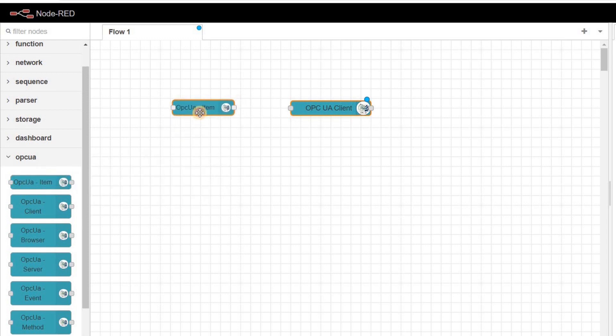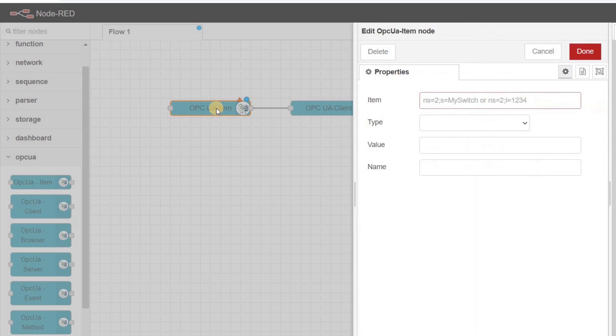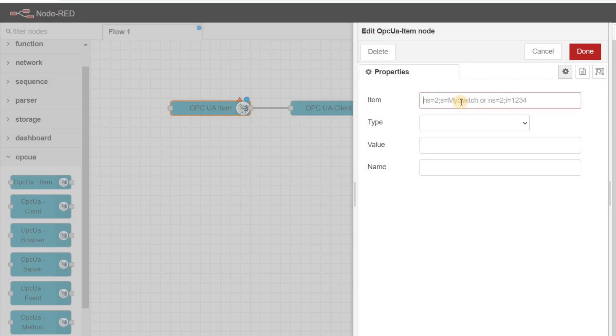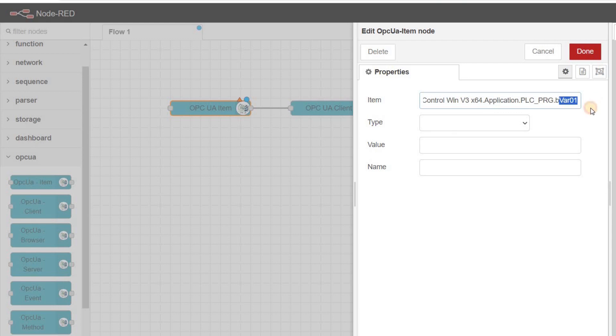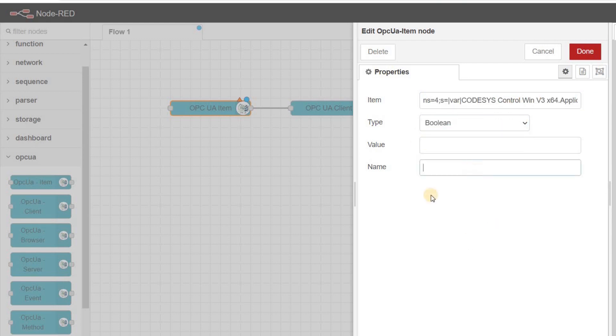With this node, we determine the variable to be read. Connect the output of this node to the input of the OPC UA client node. In the properties of this node, in the item field, copy and paste the value from the node ID field of UAExpert for each variable. I am changing the variable name to bVar01 and set the type to boolean. In the name field, I am using booleanVar01.